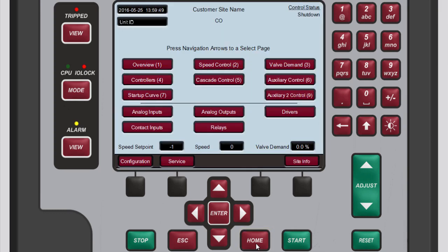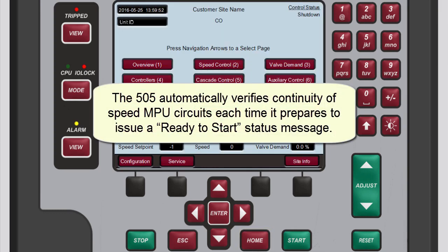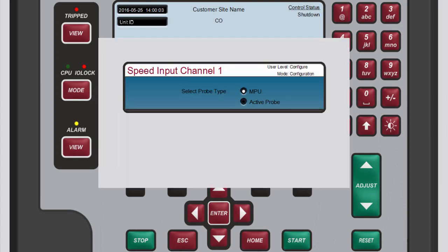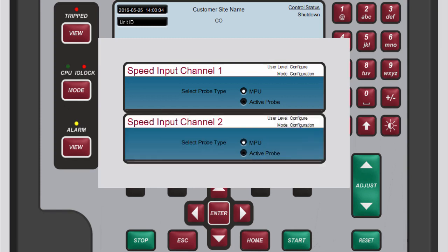Press Home again to return to the main screen. Please note that the 505 automatically verifies continuity of speed MPU circuits each time it prepares to issue a ready-to-start status message. So, if you configured one or both of the speed input channels to use an MPU and the speed is at 0, you can use the controller to perform a manual test for open wires.